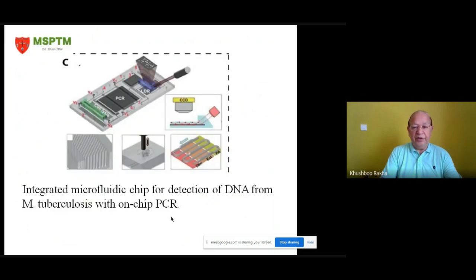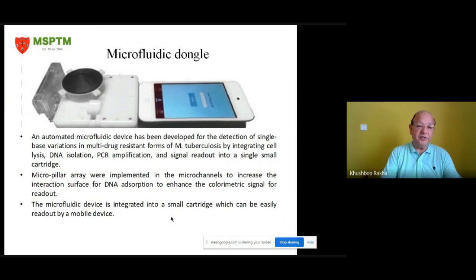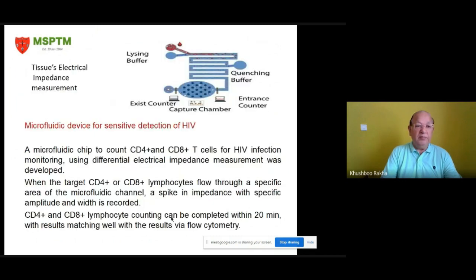This is an integrated microfluidic chip for detection of DNA from M. tuberculosis with an on-chip PCR system. The microfluidic dongle is an automated microfluidic device developed for the detection of single base variations in multi-drug resistant forms of M. tuberculosis, by integrating cell lysis, DNA isolation, PCR amplification, and signal readout into a single small cartridge. Micro-pillar arrays were implemented in microchannels to increase interaction surface for DNA adsorption and enhance the colorimetric signal for readout. The device can easily be read out by a mobile device.